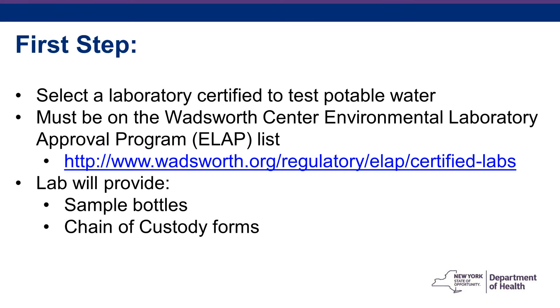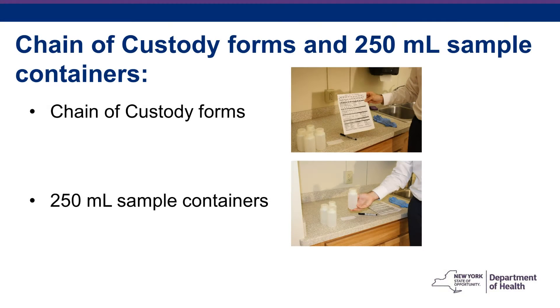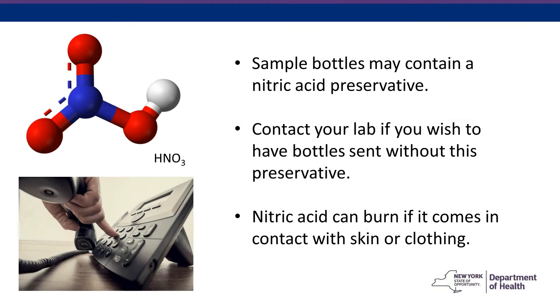School officials must select a laboratory that is certified by the New York State Department of Health Environmental Laboratory Approval Program, referred to as ELAP, to conduct lead testing in drinking water. The list of approved laboratories is located at this link. Contact the laboratory to obtain chain-of-custody forms and 250-milliliter wide-mouth plastic sample containers. If you prefer sample bottles without the nitric acid preservative, make sure to discuss this in advance with the lab before they send out your shipment.